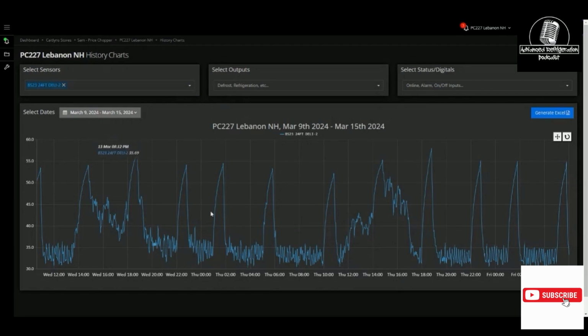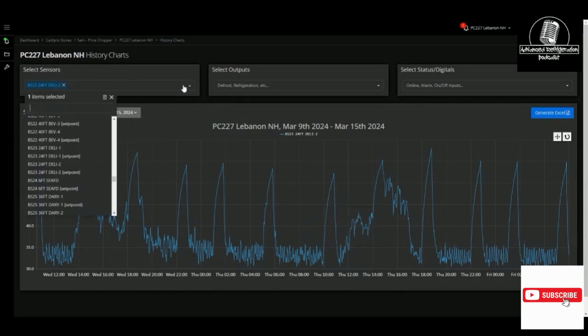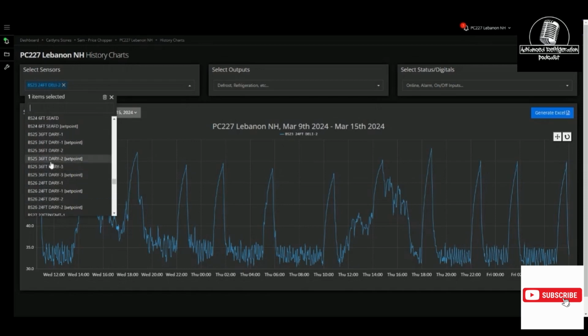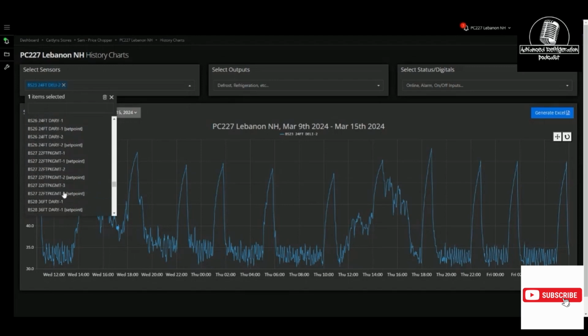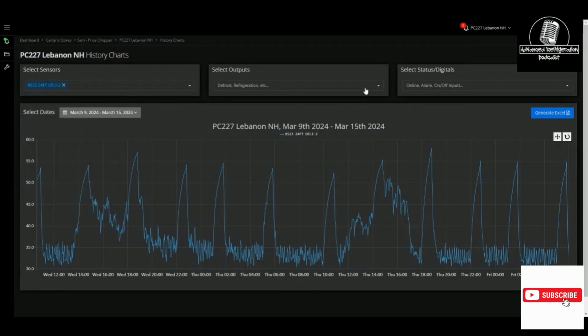As soon as this system came out of split, it was low in refrigerant. So we had recently repaired a leak 2 months ago that we had found in a produce cooler. And we added refrigerant to it. But when the system's in split, you never really know if you've added enough refrigerant, right? When you're killing half the condenser up here. You also don't want to just add 500 pounds. But we run that line where, all right, add enough now, and then we're going to keep a good eye on it. We want to keep usually a ball on our receivers at all times. But anyways, this thing was really showing when it came out of split. So you can overlay this with your ambient temperature, and then you'll see that it goes up. So anyways, there's a lot of really good troubleshooting opportunities with this history chart.